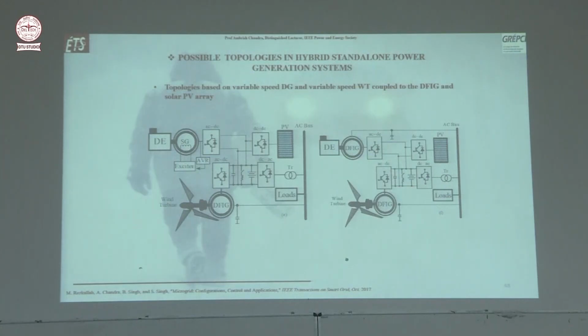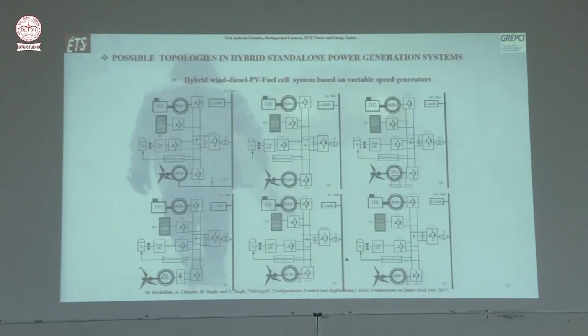And again the same thing. Suppose you have a DFIG machine here for the wind turbine, rotor side 1/3 capacity AC to DC converter. For the diesel engine you are having a doubly fed induction generator, the stator is connected here and the rotor side is 1/3 capacity, but this power is coming to the DC bus. Moreover, power from PV is also coming to the DC bus. The size of this inverter will increase.